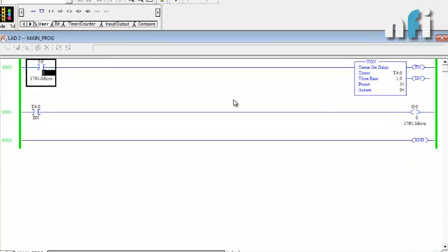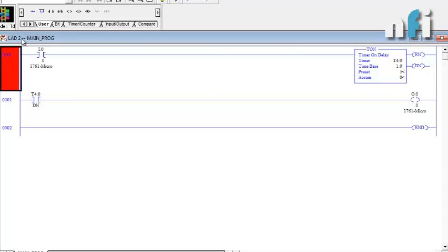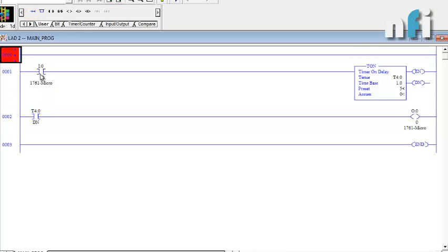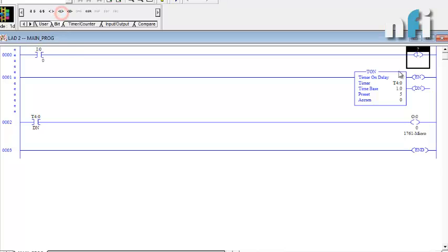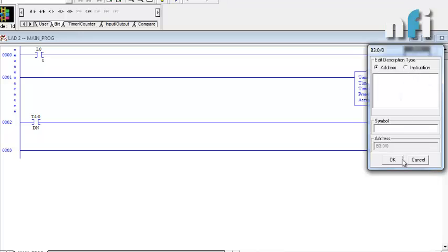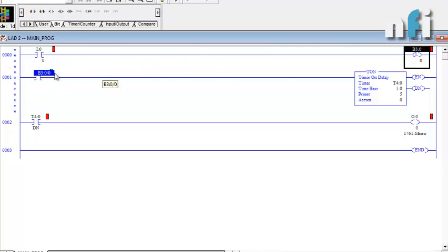Suppose I need a program where if I press this button just once — not hold it for five seconds — the output should still be on after five seconds. We know that if I press I0 and release it, the timer will reset. So in that case, we'll use internal bits of Allen Bradley. I'll add another rung with the I0 contact and latch a bit — an internal bit with address B3:0/0 — which will be latched when I press I0.